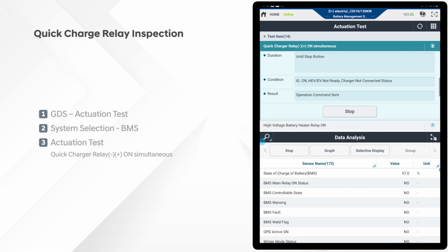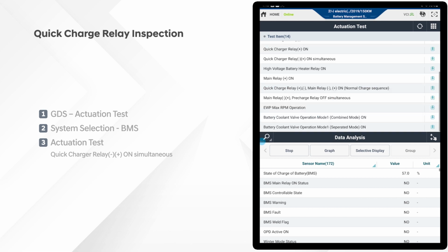Did you hear that? This is the sound indicating that the Quick Charge Relays plus and minus are set to on. Even though you can hear a clicking sound, the relay may have a problem along the contact point. That's why a continuity test should be performed. But if there's no click sound, the relay is faulty.